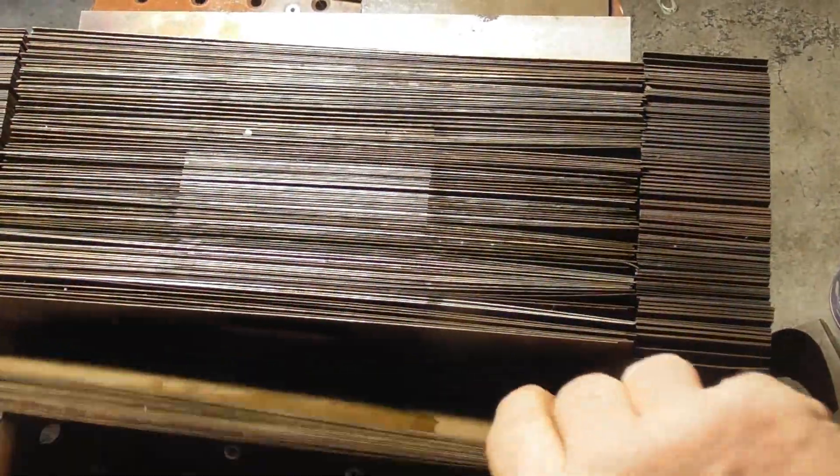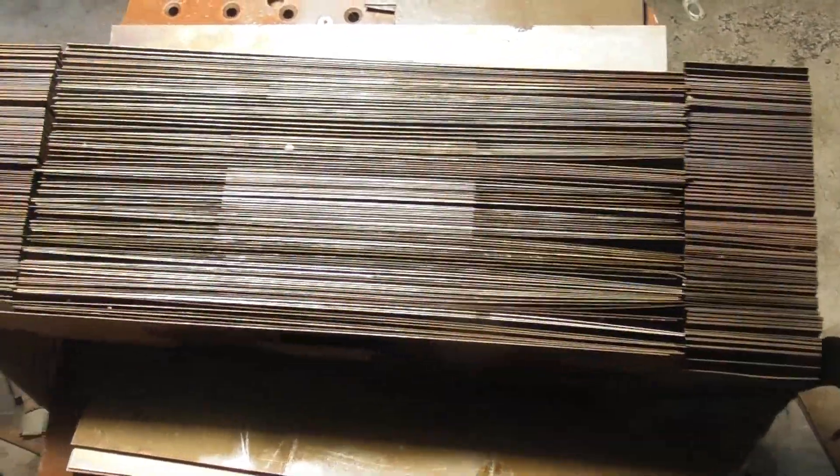So as you can see it's stuffed up a little bit — I've still got some of these left over. Actually on the camera it shows up really well. This middle cluster, there are still two plates together, so I need to separate this out and slide an additional plate in there. So I'm going to try that and tidy that up. You should have one plate and then it's staggered with the other one of the inner core. I need to tidy that middle part up.